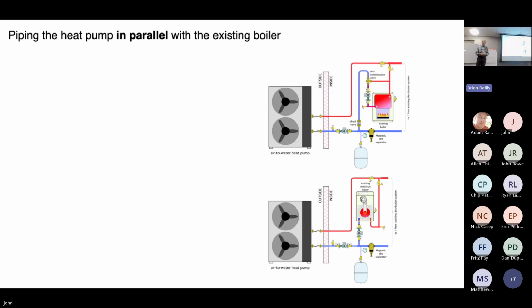In fact, there are companies in Europe that sell controls where you input that information and the controller will make the switch for you. And for some of the heat pumps, there's one product that is likely to be on the market next year that has that as an internal function. It's built right into the firmware. So if there is a boiler in the system, it has the contacts to initiate the boiler, and it can do the calculation based on the economic balance point. So, yeah, controls can do a lot.